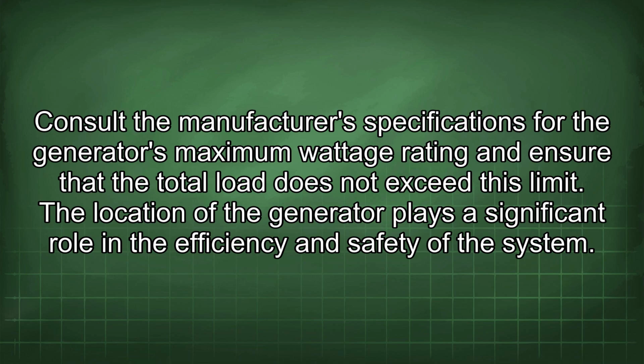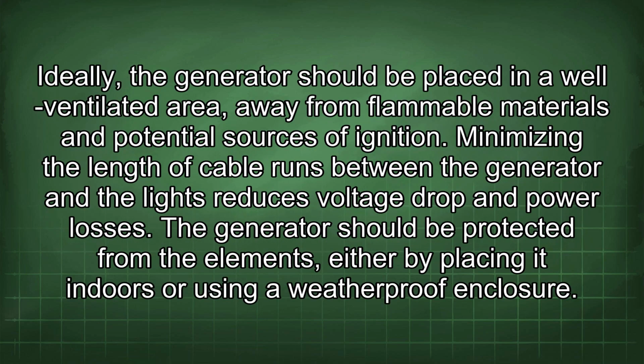limit. The location of the generator plays a significant role in the efficiency and safety of the system. Ideally, the generator should be placed in a well-ventilated area, away from flammable materials and potential sources of ignition. Minimizing the length of cable runs between the generator and the lights reduces voltage drop and power losses. The generator should be protected from the elements, either by placing it indoors or using a weatherproof enclosure.